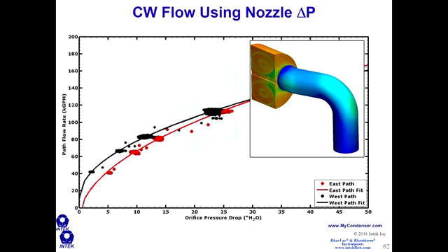Again, if you're to do this the right way, you do some CFD analysis. You do a model of the water box and the piping connected to it. You find regions for taps that will give you the best performance as far as signal range, so usually the highest DP. You also want to avoid areas of vortices, and you want to avoid areas that can cause debris buildup in your taps.